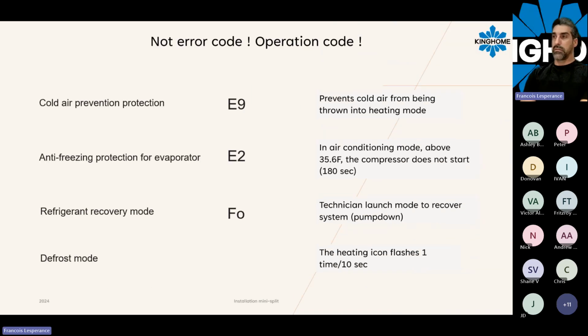There are some codes that are not error codes but operation codes. So if you happen to see E9 on the head and you're asking why, or looking at the error codes list for what an E9 is, it's not an error code, it's an operation code. That means the system is now in cold air prevention protection. This operation code will happen in heating. The system is preventing the blower from starting because the temperature of the inner coil is too cold.